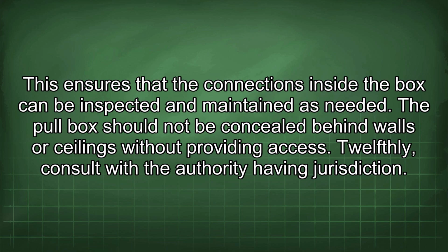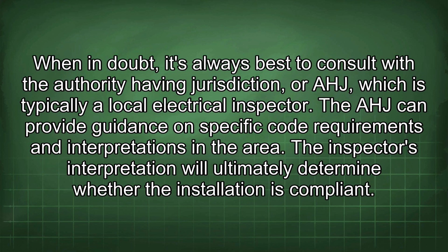The pull box should not be concealed behind walls or ceilings without providing access. 12thly, consult with the authority having jurisdiction. When in doubt, it's always best to consult with the authority having jurisdiction, or AHJ, which is typically a local electrical inspector. The AHJ can provide guidance on specific code requirements and interpretations in the area. The inspector's interpretation will ultimately determine whether the installation is compliant.